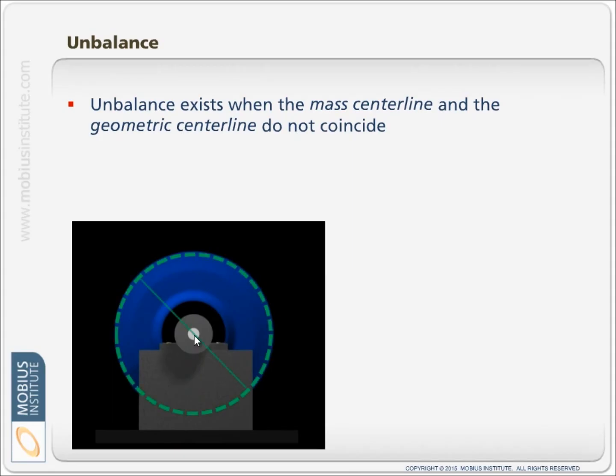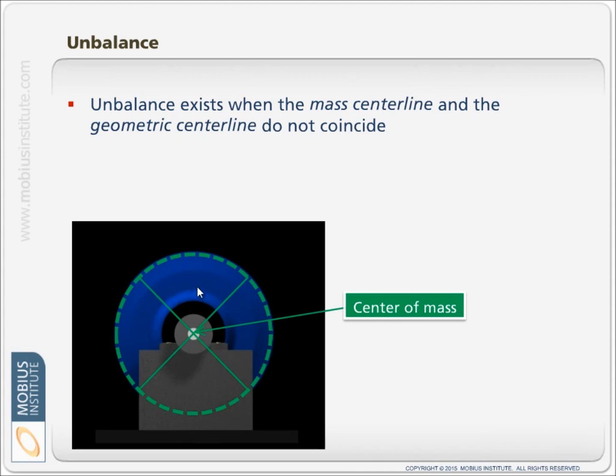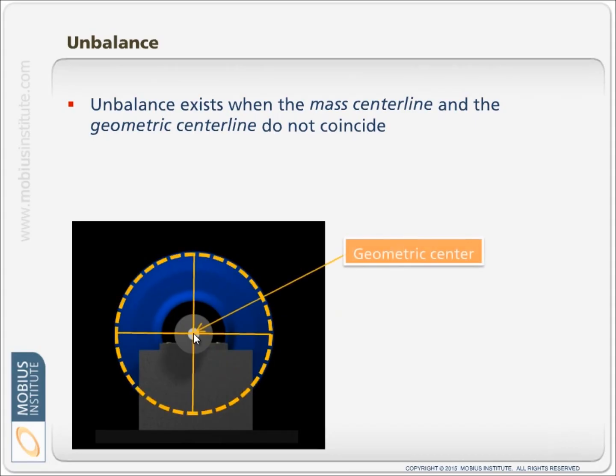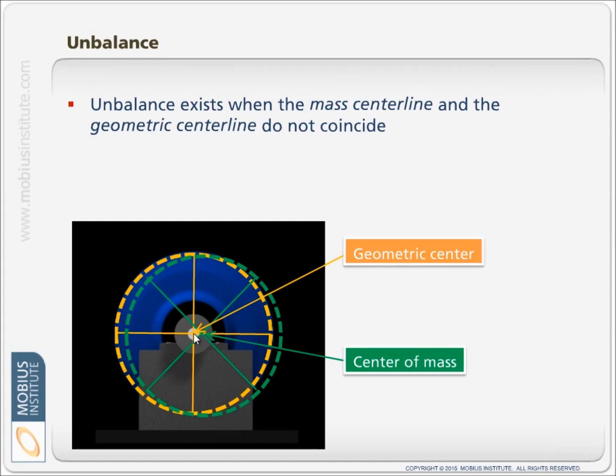Our mass centerline should be in the same location. If all the mass is evenly distributed around our machine, then the center of mass would be right through the center of the rotor as well. But when that is not the case — when the geometric center and the mass center are not equal — then when we spin the rotor it will wobble, and that is unbalance.